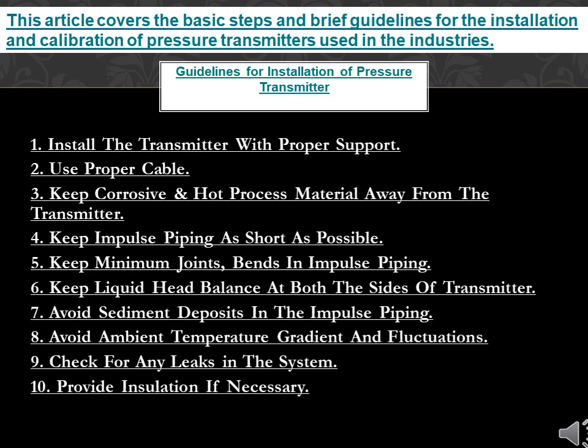Keep impulse piping as short as possible. Keep minimum joint bend in impulse piping. Keep liquid head balance at both the sides of the transmitter. Avoid sediment deposit in the impulse piping. Avoid ambient temperature gradient and fluctuation. Check for any leakages in the system. Provide insulation if necessary.